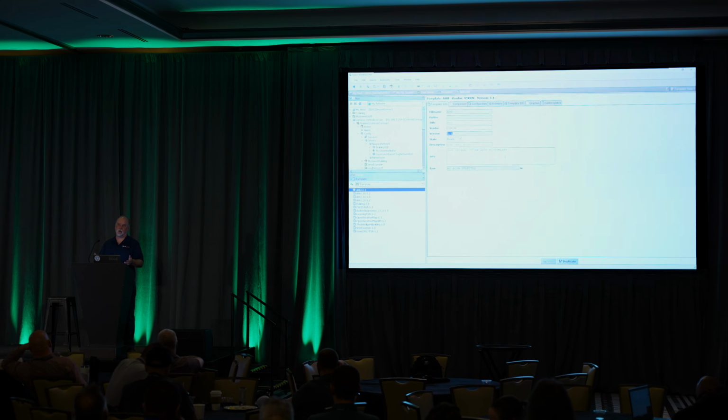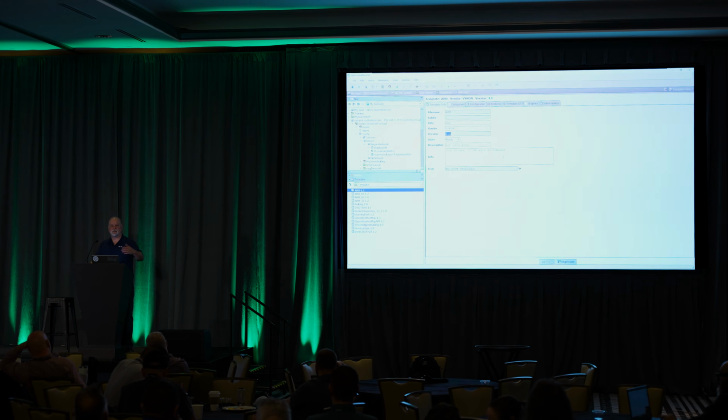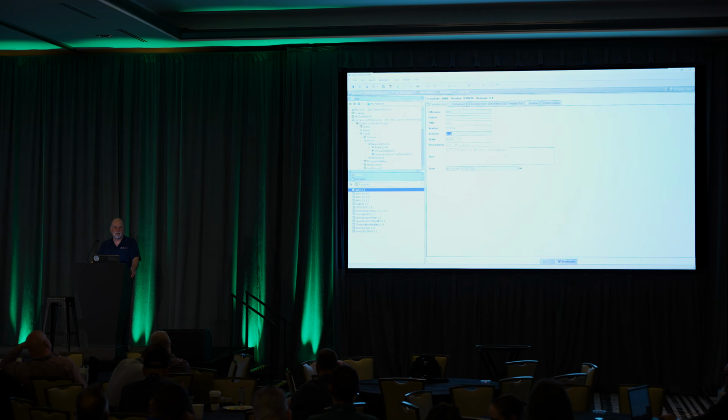And what this allows us to do is, if I've got 100 VAVs or 100 air handlers or whatever in a station, and I need to make a change to them, if I've deployed them with a template, all I have to do is go modify that template, and then I go into the station and I redeploy or upgrade it. And that'll make that change across all the devices that exist in the station. So it's an engineering efficiency thing. I don't need to go to 100 wire sheets and go make the same changes. I make the change one time in the template, and then I tell it to upgrade the template. So it's an efficiency thing as well as a standardization thing, right?